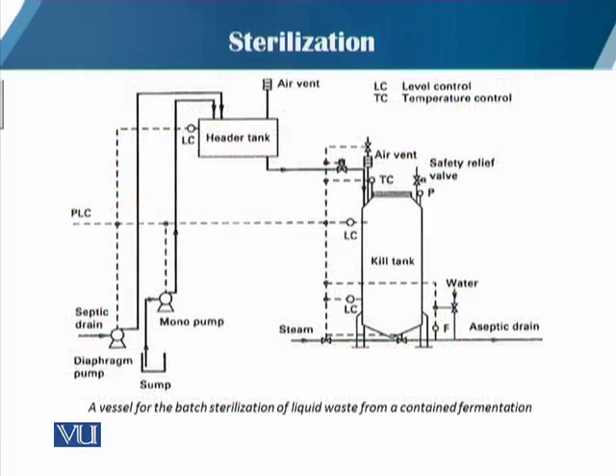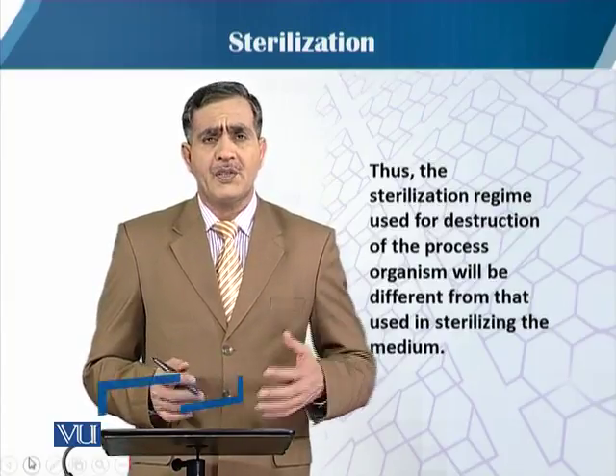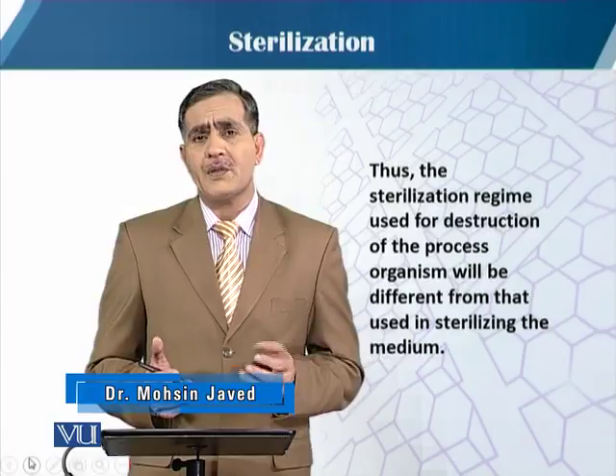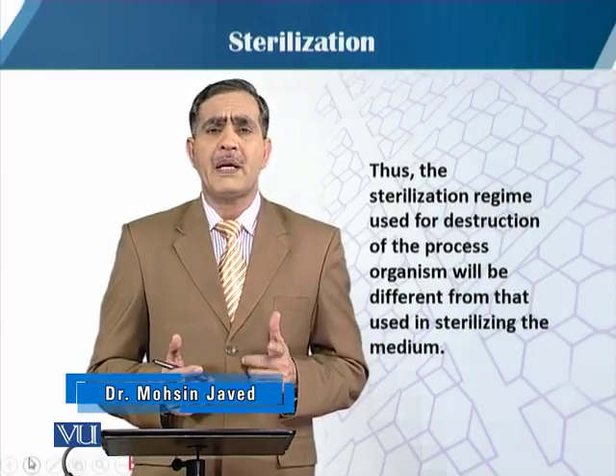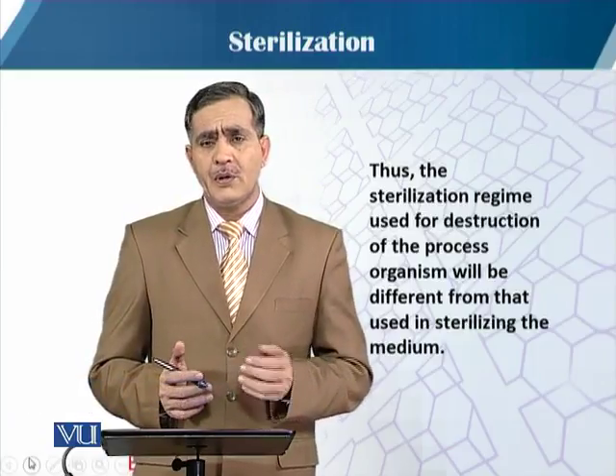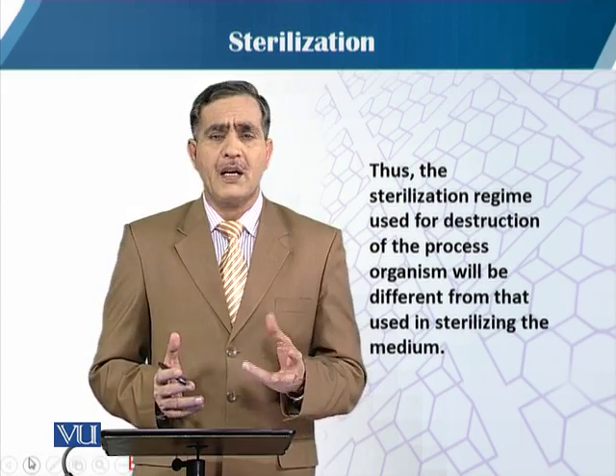You can see in this slide the different steps involved in treating such liquid waste. Here is the header tank, and this is the kill tank, which we call the treatment tank. These are the different lines, and you can see the level control and temperature controls. So this is a vessel for the batch sterilization of liquid waste for a contained fermentation. Thus the sterilization regime used for the destruction of the process organism will be different from that of the sterilization process, because the sterilization process is controlled with respect to Bacillus stearothermophilus, as I have already told you, but in this case we have to run the process according to the process organism.